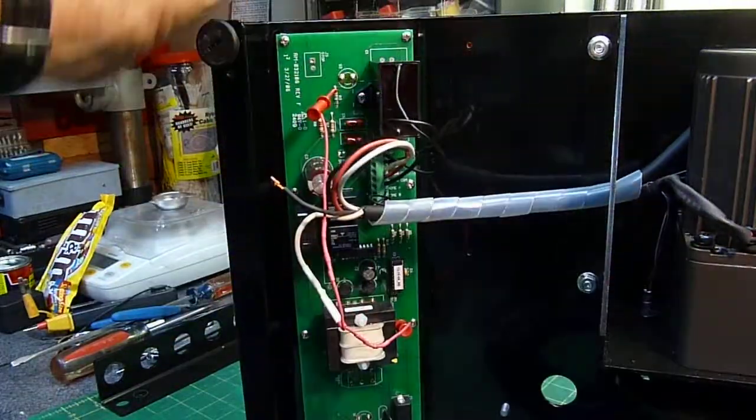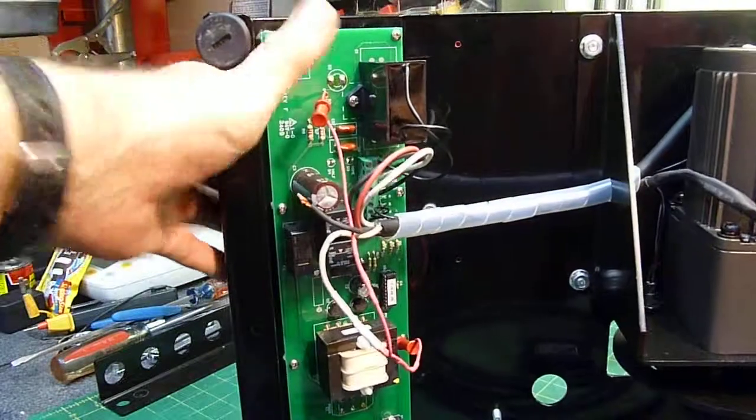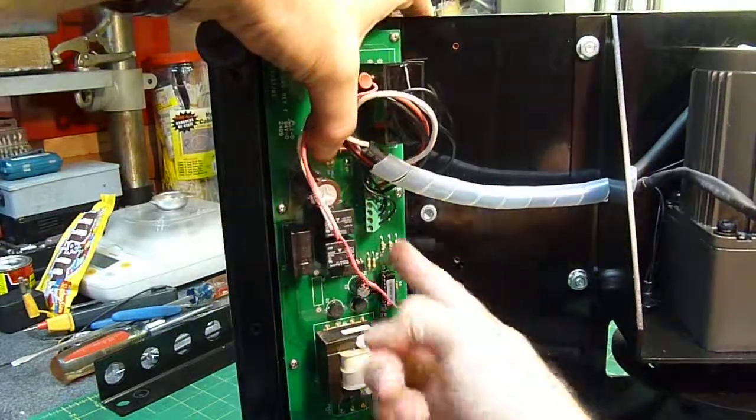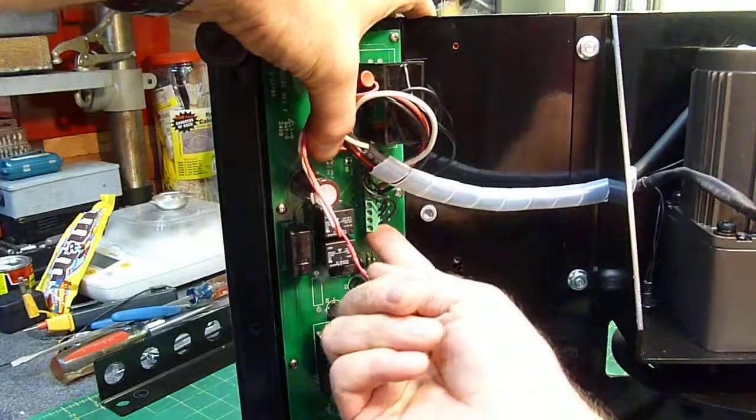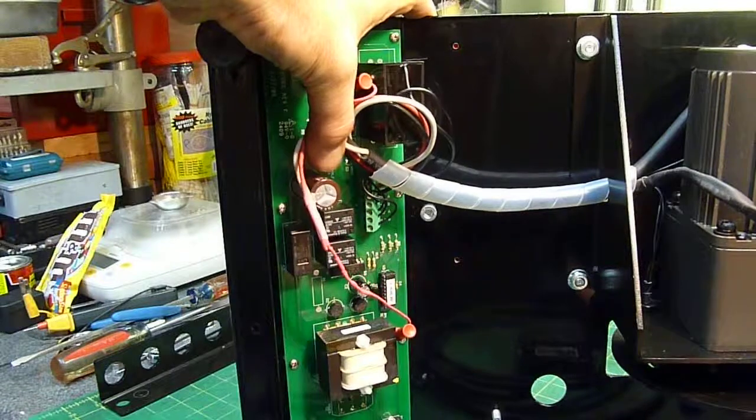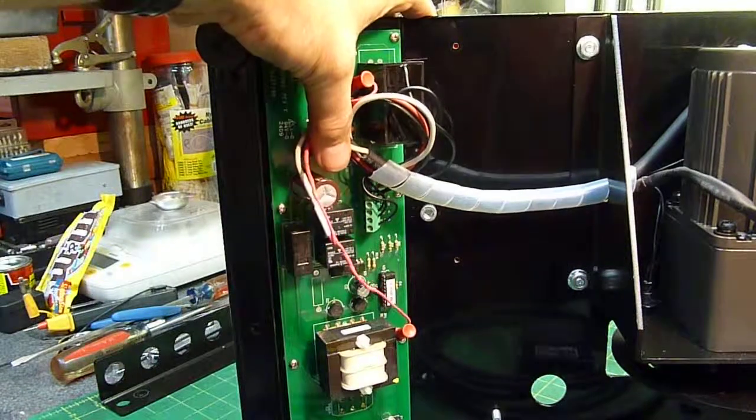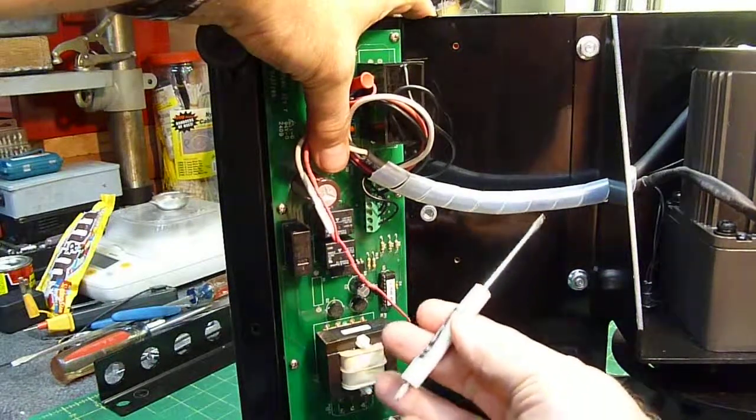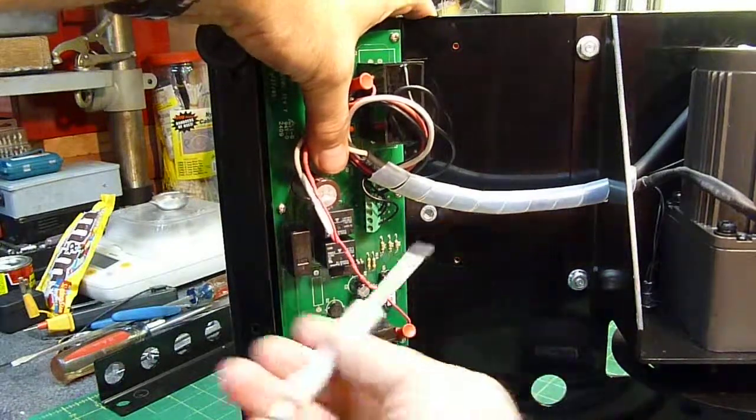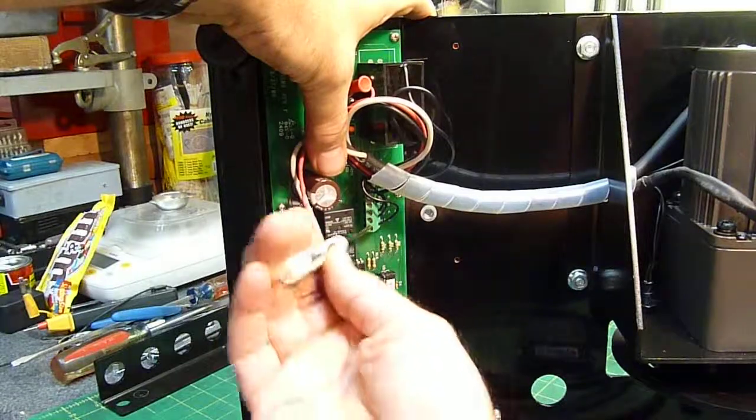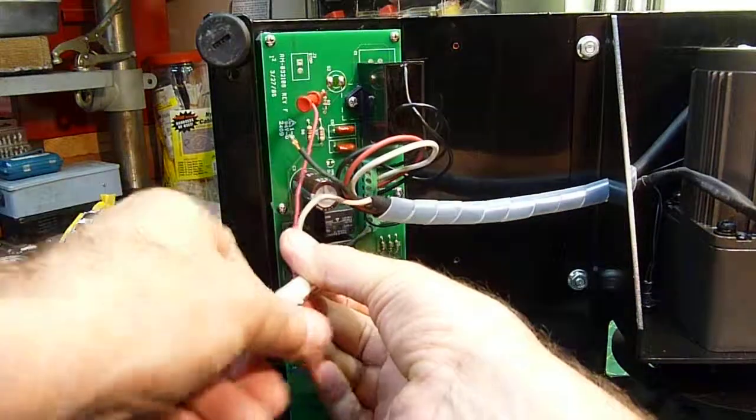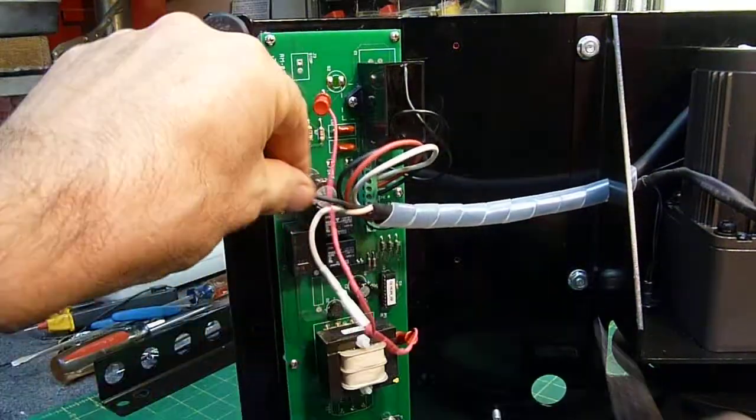And then there's one ground wire that we have to hook up. And it's going to go under the innermost terminal here, which is actually marked half B. So you'll need an electronic screwdriver or some sort of a small screwdriver. And you open this screw up about three or four turns. The screw's not going to come out.